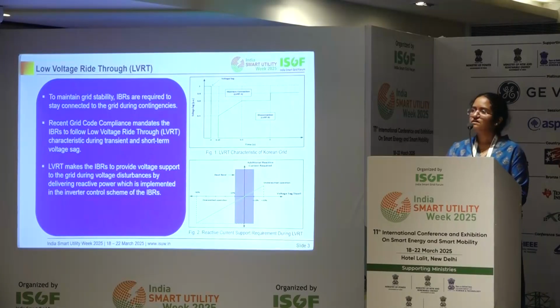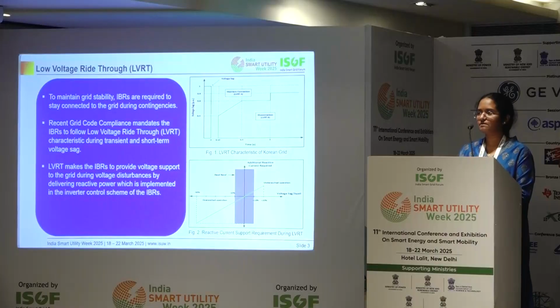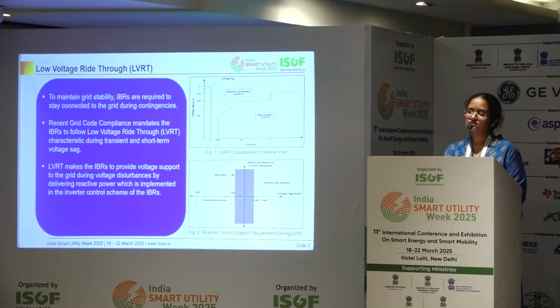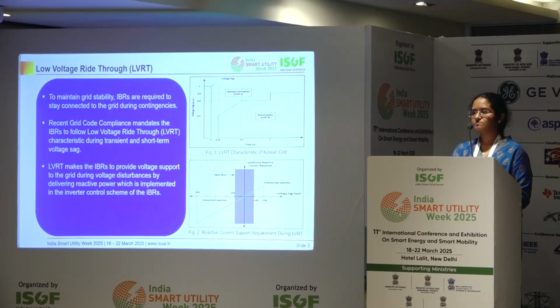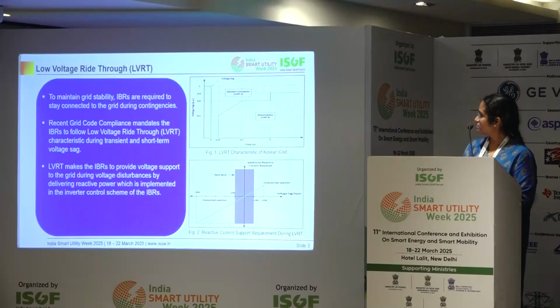If you consider the below graph, LVRT does not just do voltage monitoring, it also injects the reactive power required for the system. As we have huge power systems, power grids, if there is any requirement of reactive power due to the voltage fluctuations, it must be provided only by the IBR. It cannot be pulled from the infinite grid. If it is pulled from the infinite grid, it creates much more problems. So LVRT should also help with the reactive power compensation.